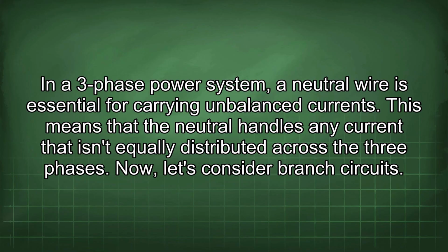In a three-phase power system, a neutral wire is essential for carrying unbalanced currents. This means that the neutral handles any current that isn't equally distributed across the three phases. Now let's consider branch circuits.